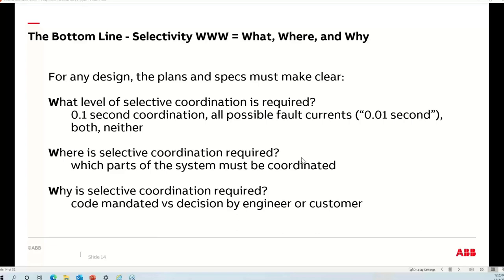The 'why' may strike some as odd, but it's not uncommon to see requirements in specifications that exceed what the NEC would dictate, or in some cases are less. When there's no clarification of the why, it generates questions: was something missed, something not understood, or is the engineer simply asking for more coordination than the NEC requires — which is certainly allowed. If you're asking for less than what the NEC allows, there should be an AHJ exemption. So put the why, especially if you're doing something that isn't standard to code.